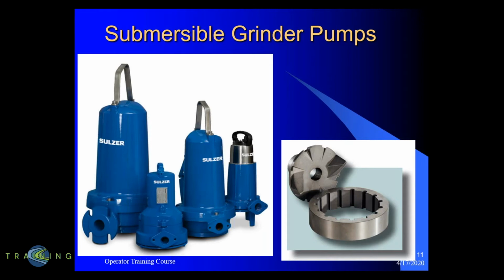And then usually your discharge is between 1.25 inches and 2 inch, which means that you can use small diameter force mains. So instead of passing a 3-inch solid, we're grinding it up, slicing it up, passing it through a small throatlet, and pushing it through a 1.25 to 2 inch pipe in order to keep it moving throughout the system.